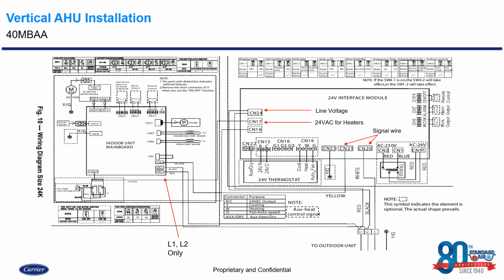Of course, this information is also in the installation manual as well, and we're helping configure that. But just as a rule of thumb, it's nice to be aware of the two most important ones, in my opinion, which are SW1-1 and SW1-2, especially on brand new installations, to ensure you're not getting a communication code and troubleshooting an issue that really isn't there, and it ultimately comes back to how a dip switch is set.